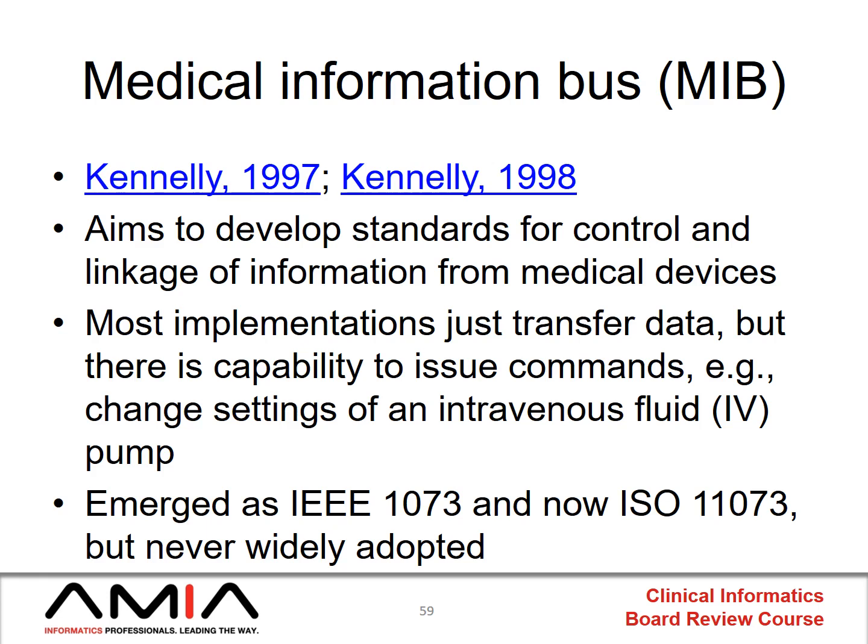Most implementations of the Medical Information Bus just transfer data between devices, but the standard itself has the capability to issue commands, and as such, one could, for example, remotely change the settings of an intravenous fluid pump. The Medical Information Bus became the IEEE 1073 standard, and then was superseded by an international standard of ISO 11073.